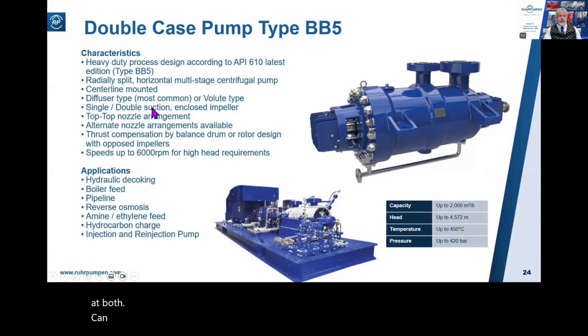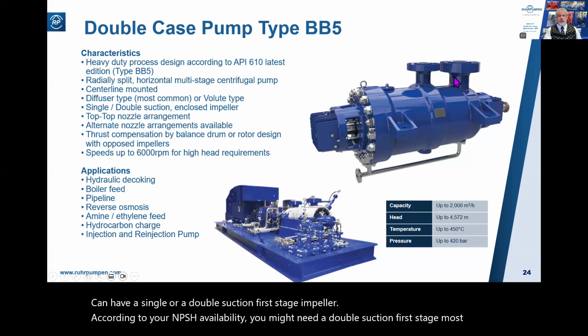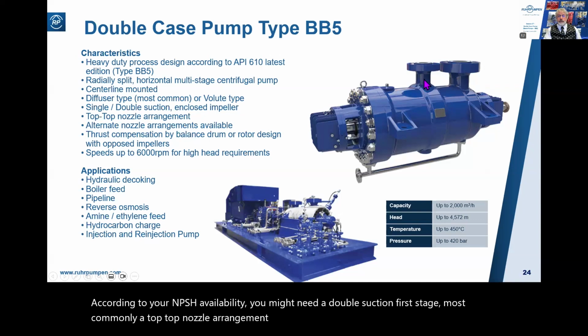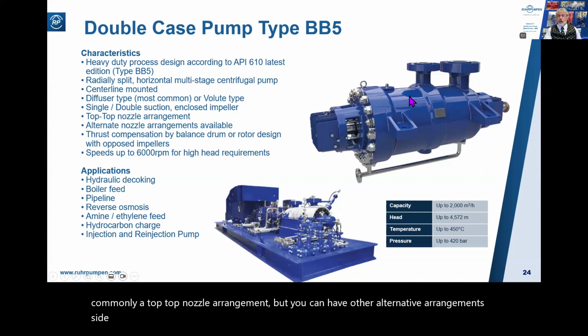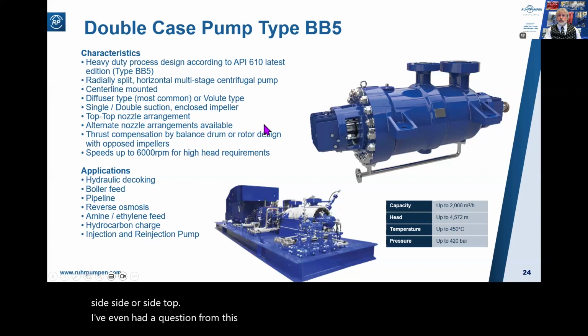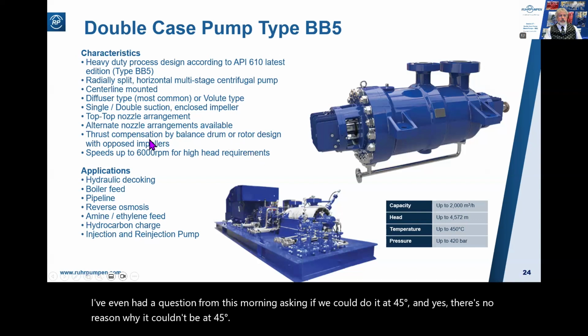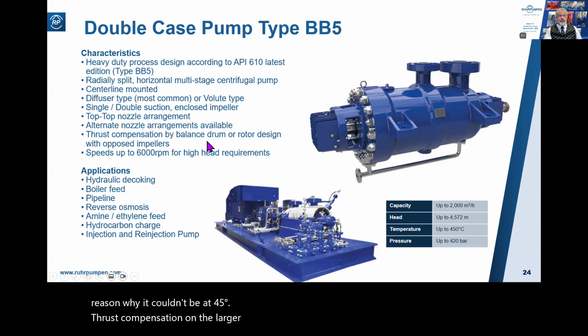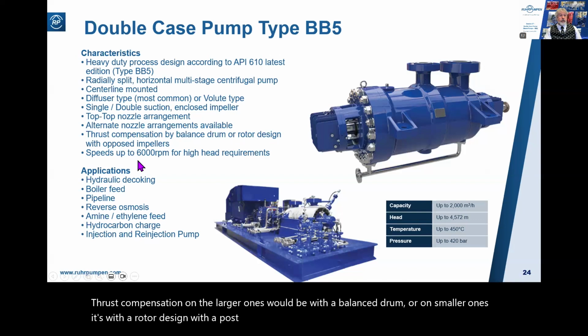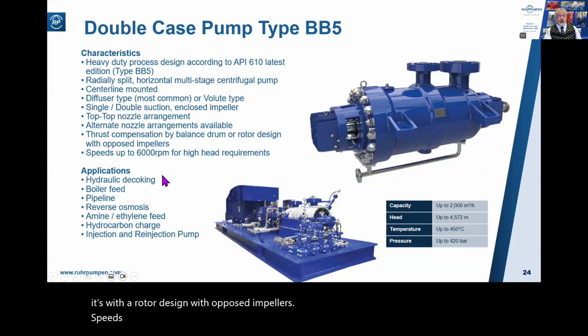Can have a single or a double suction first stage impeller. According to your NPSH availability, you might need a double suction first stage. Most commonly, a top top nozzle arrangement, but you can have other alternative arrangements, side or side top. I've even had a question from this morning asking if we could do it at 45 degrees. And yes, there's no reason why it couldn't be at 45 degrees. Thrust compensation on the larger ones would be with a balance drum, or on smaller ones, with a rotor design with opposed impellers. Speeds up to 6,000 RPM, and these are the typical applications.